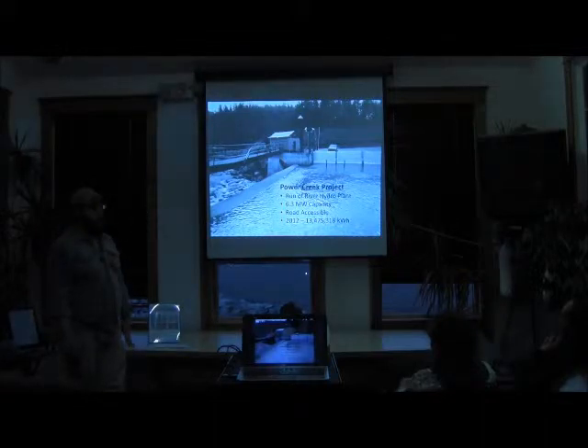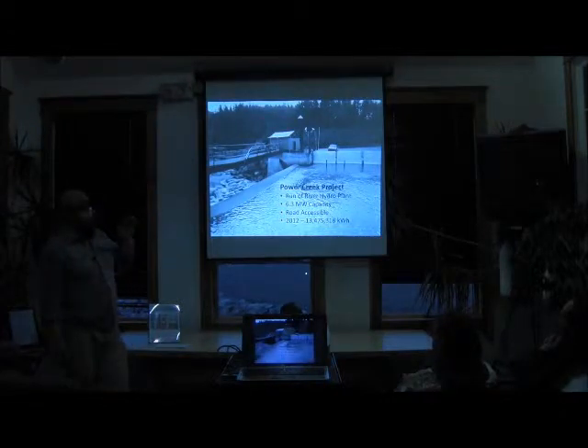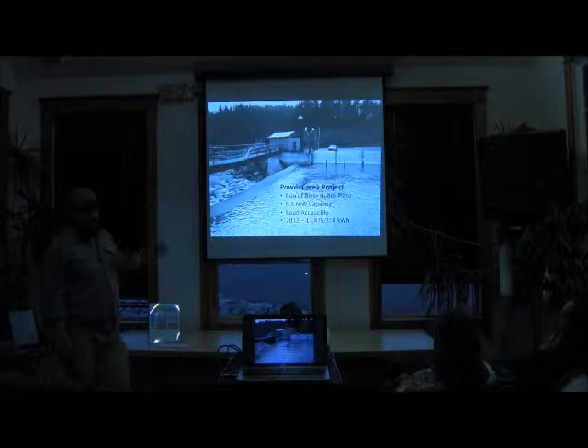Are there some days where it doesn't produce any electricity at all? Yeah, this last couple of years, there have been some periods when the temperature drops, like in March, April. Once the flow gets too low, there's not enough flow to keep the turbines going. That's down around 8 CFS. We get below 8 CFS, and we can't run the plant. There's not enough water, and it's rated up to 350 CFS.